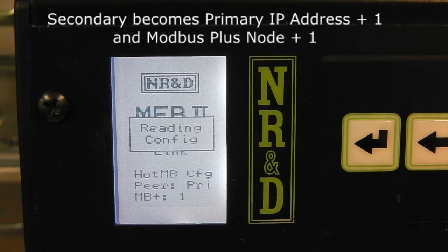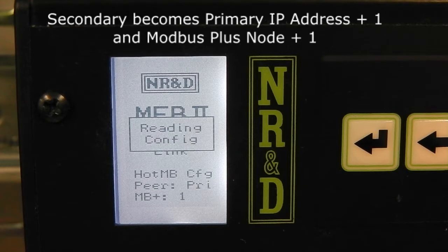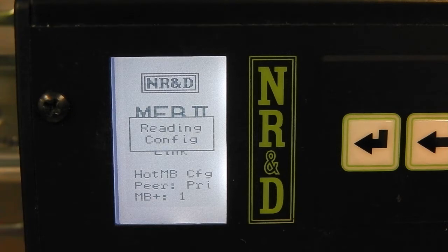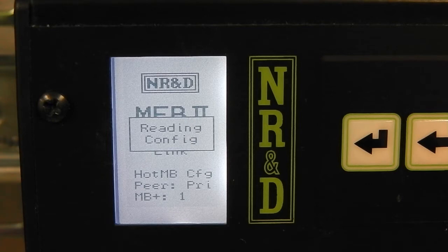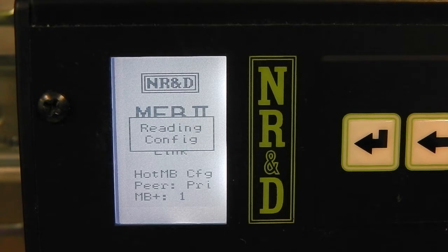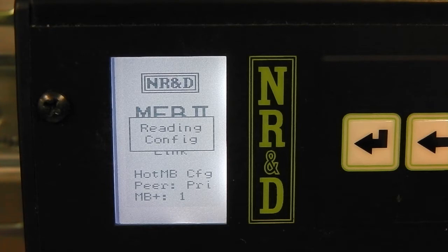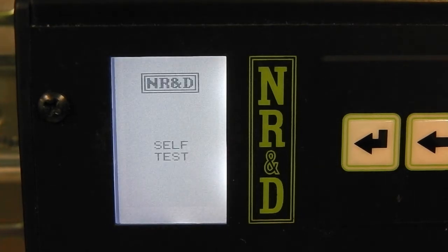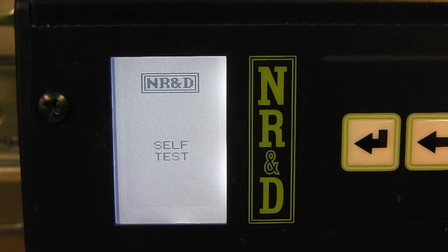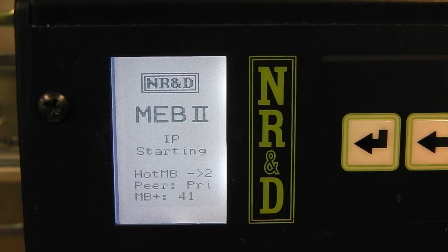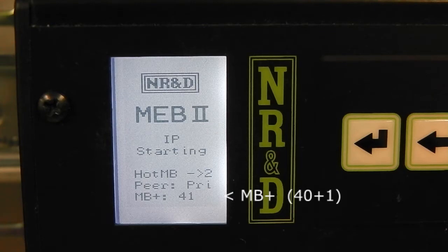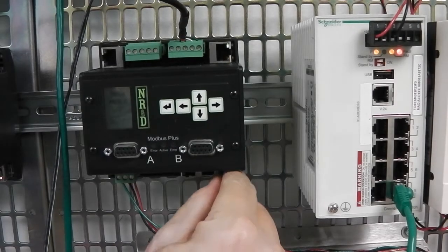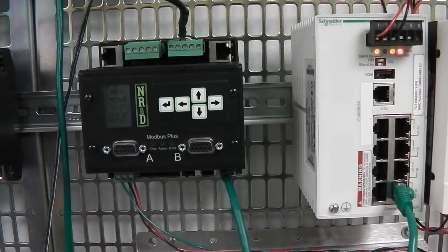The secondary unit adds one to the primary's IP address. It also adds one to the primary's Modbus Plus node. When the transfer is completed, the secondary unit reboots and assumes normal operation. The Ethernet and Modbus Plus cables may now be connected to the secondary.